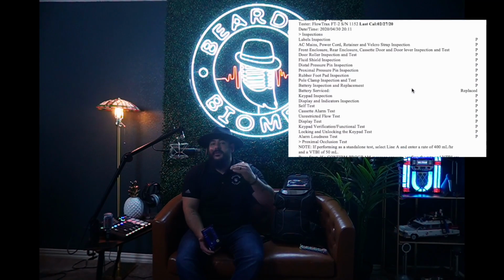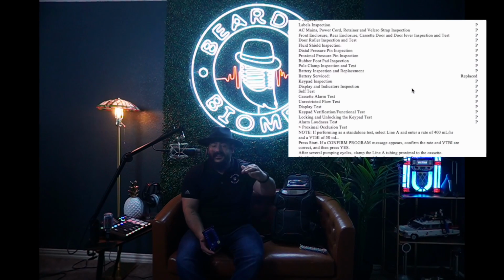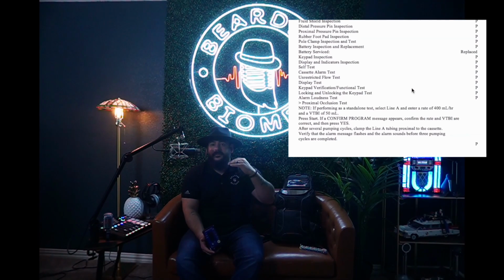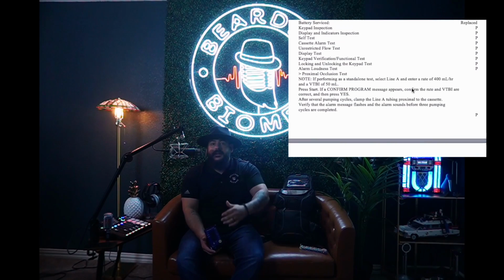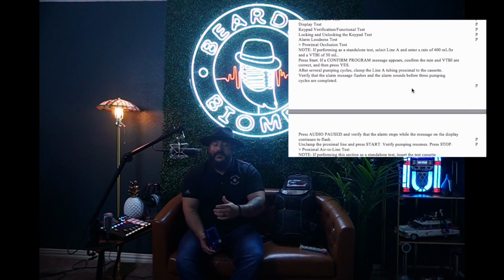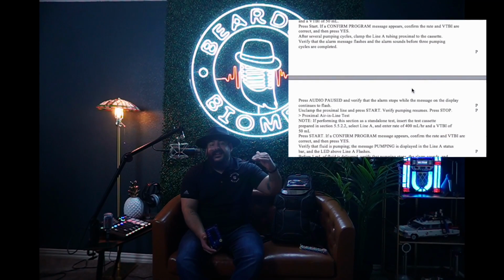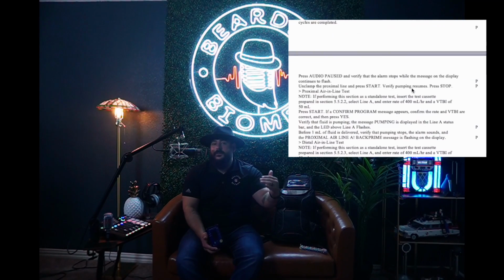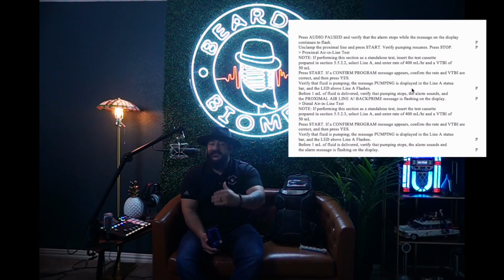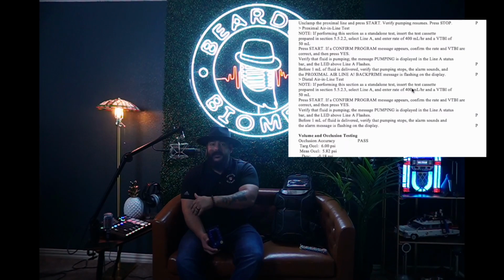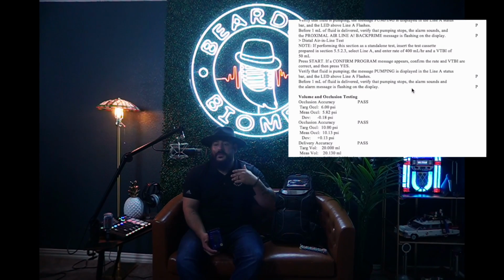But what's cool about the report is it lists out each test that you got, even for electrical safety, all of your pressure occlusion, stuff like that. But it lists at the very top of that report the test equipment used, the ID tag on that test equipment, serial number, and the last date it was calibrated. Which, when you're speaking of like Joint Commission, DNV, stuff like that, this is putting it all in one pretty document on every single work order of every single device you're testing. So I thought that was pretty badass.